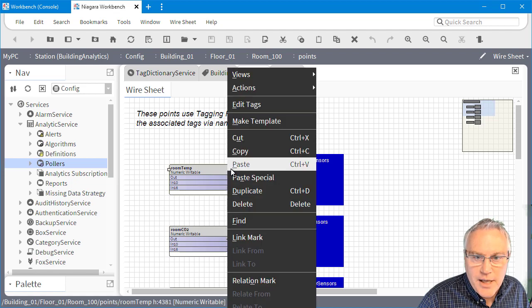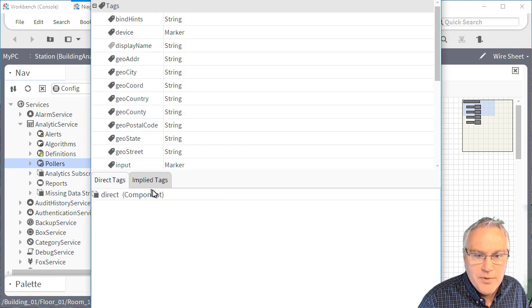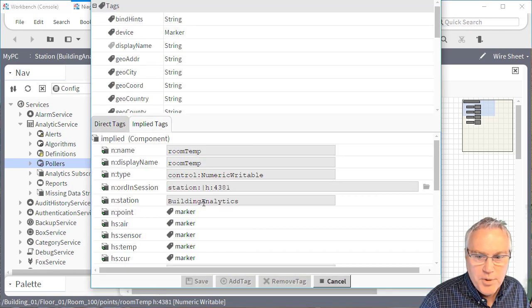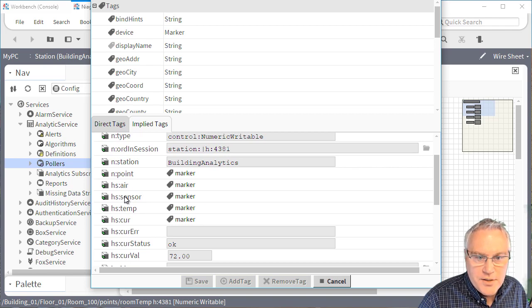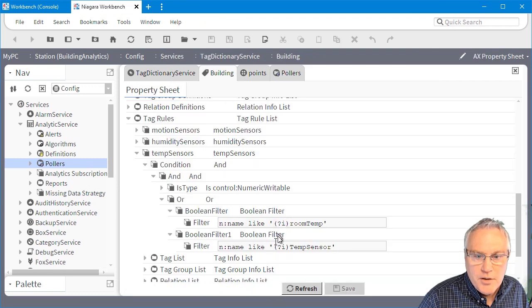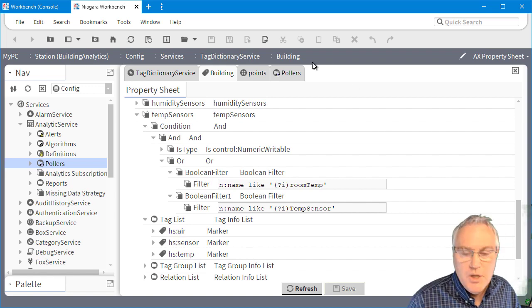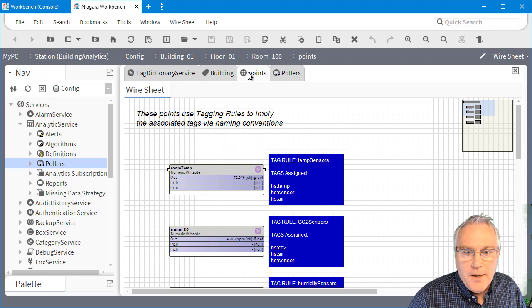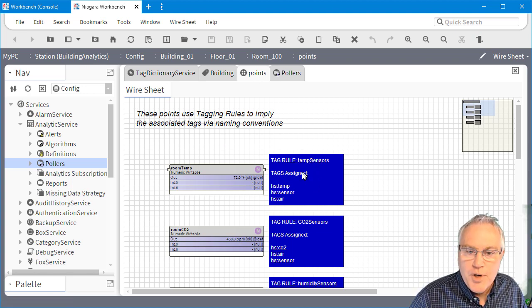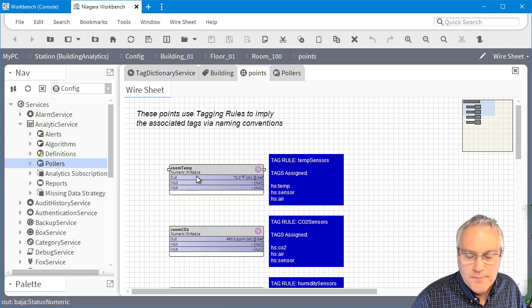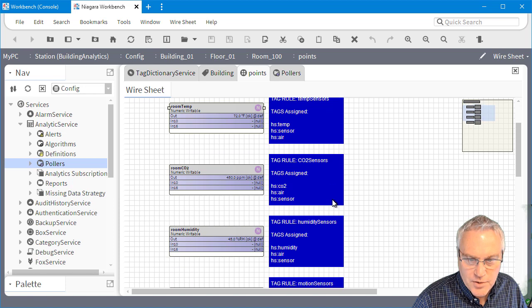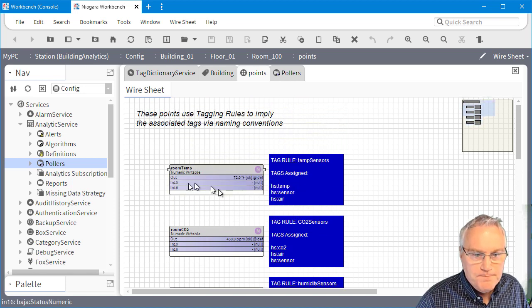Implied with the tag dictionary implied tags. So if we come down here and we look at edit tags and we go over to zoom in the window here into implied, you'll see that here's hs air, hs sensor, and hs temp. So those were part of the rule if we come down here to see what tags I imply: air, sensor, and temp. So the tag dictionary is working. I have essentially a little note here to kind of remind me that I have rules in place to tag the appropriate temperature. I just did that for the station. I don't usually do that as the best practice because I know those rules are engaged.